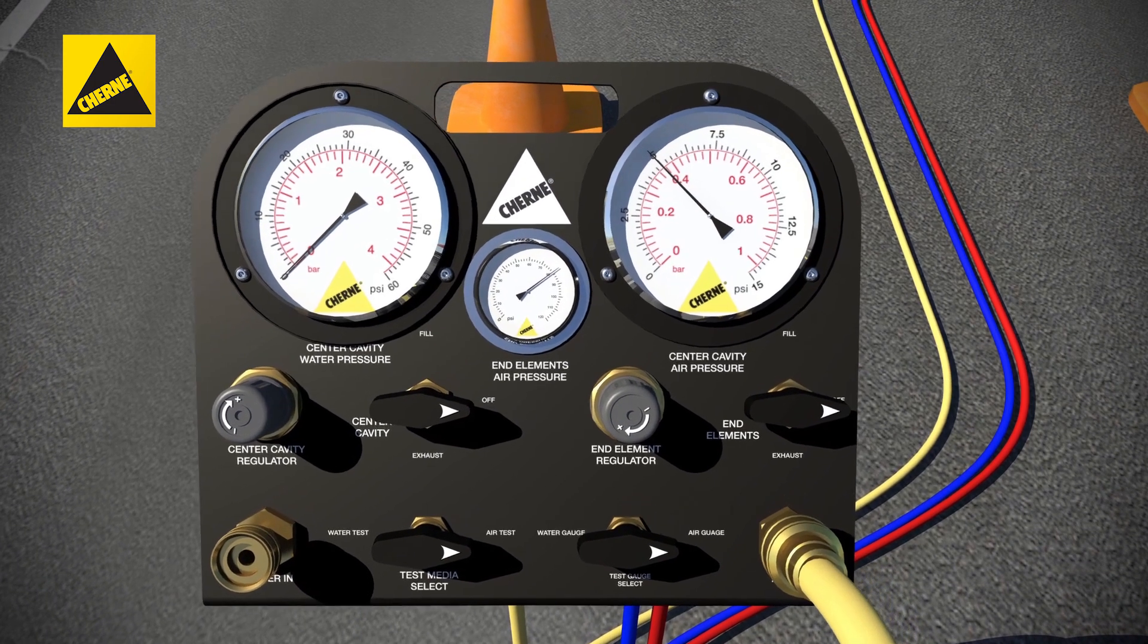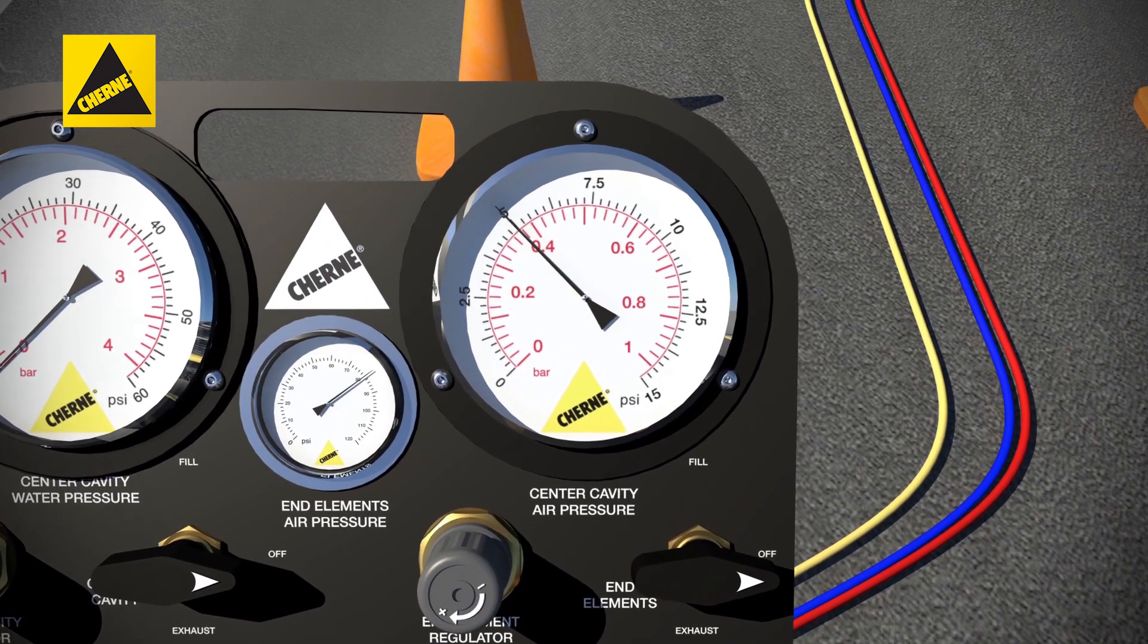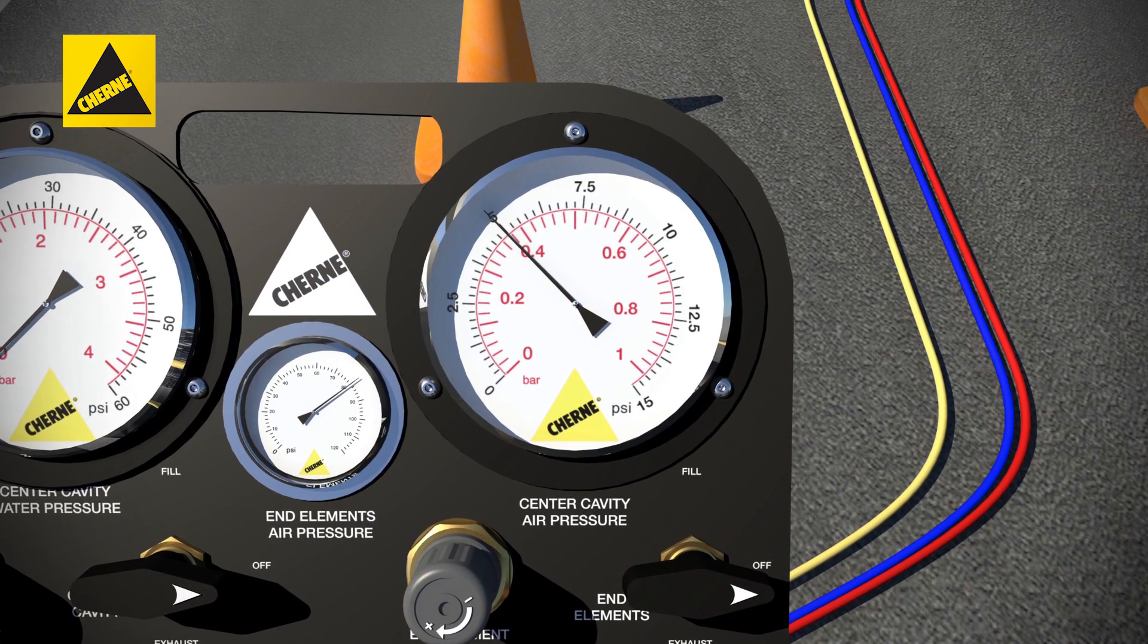Monitor the test pressure gauge to determine the amount of time it takes to drop psi. If the joint holds its pressure for the specified amount of time, it passes. If there is a loss of air pressure in excess of 1 psi during the required test period, future repair will be necessary.